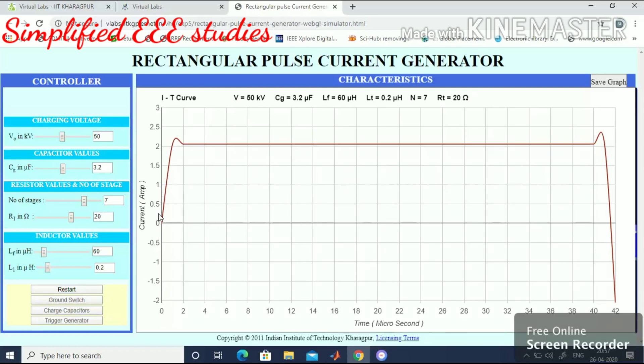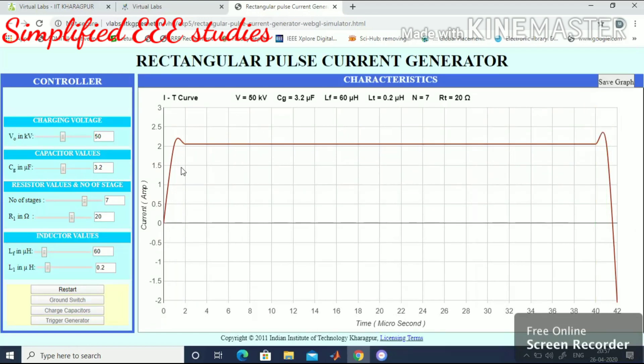Now I'm getting the waveform — a rectangular pulse. The magnitude is visible on the y-axis, and the x-axis shows the time period in microseconds, which can also be expressed in milliseconds. The parameters are: charging voltage 50 kV, capacitance 3.2 microfarad, LF (wavefront inductor) 60 microhenry, LT (wavetail inductor) 0.2 microhenry, N = 7 stages, and R (wavetail resistance) = 20 ohm.